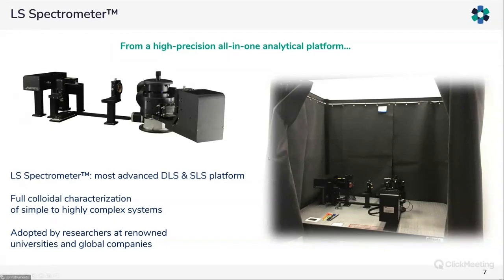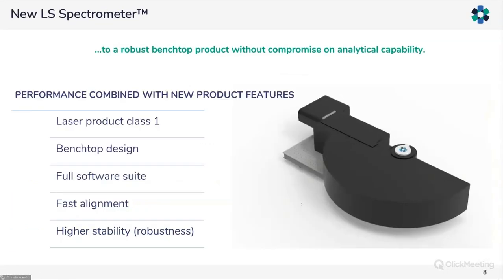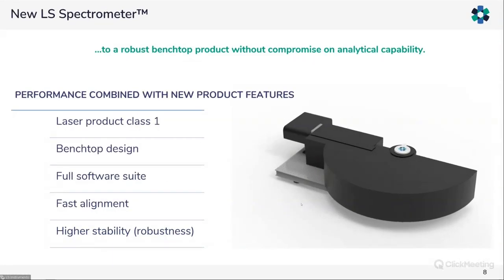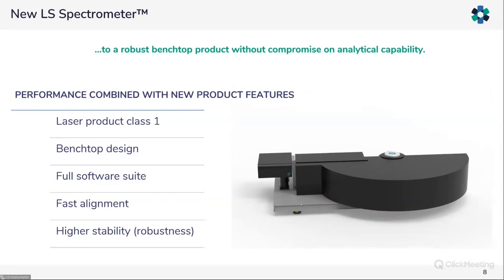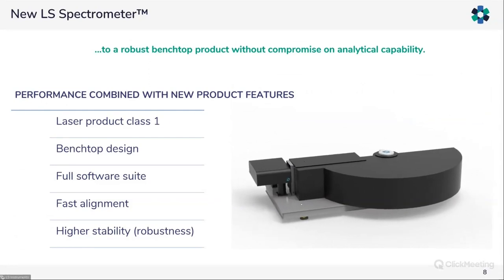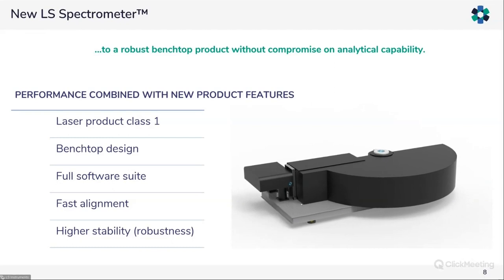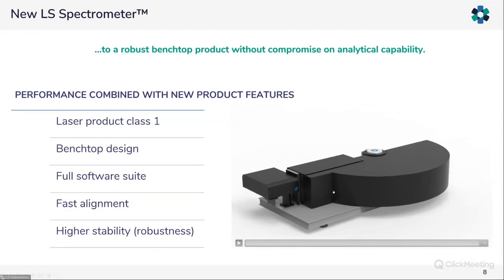The legacy of the LS Spectrometer also involved an open design, which sometimes required laser curtains and installation on an optical table. As of today, we are proud to announce that while keeping all the analytical capabilities, we have reduced these restrictions and are now offering a fully robust benchtop product without compromising any of the instrument's power. This new closed design enables laser class 1 operation, and the instrument does not require installation on any specific equipment — any standard lab bench can be used.